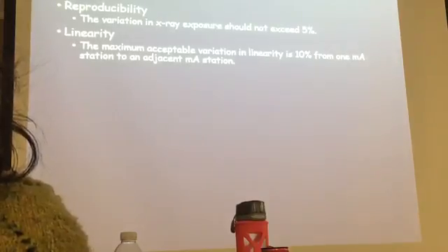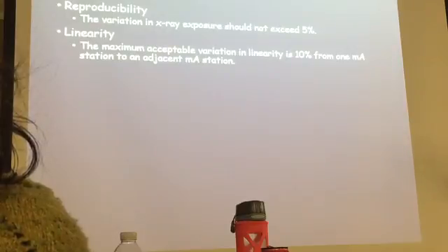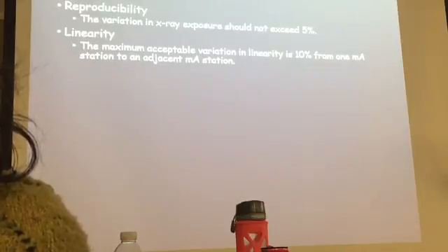If my original technique was 10 and I go up to 20, what do you expect? It should increase to maybe twice the exposure. Yeah, so if I had 5 the first time, I should get 10 milliroentgen. Make sense? Yeah, because you doubled the mAs. Exactly.